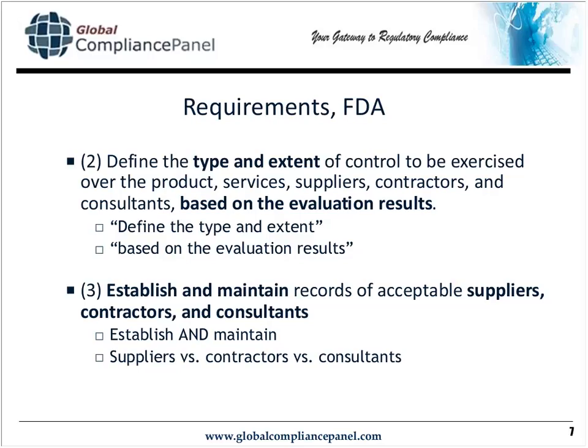So your type and extent of control over the product is usually an incoming inspection, an incoming test, or an incoming verification. But the type and extent of control that you exercise over the actual supplier of that component is obviously related, but a different type of control. Over what period of time do you annually assess these suppliers? By what method do you assess these suppliers?